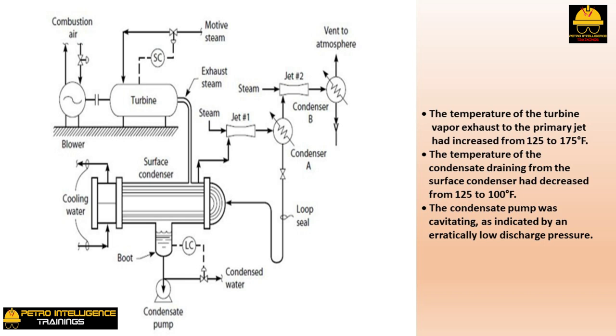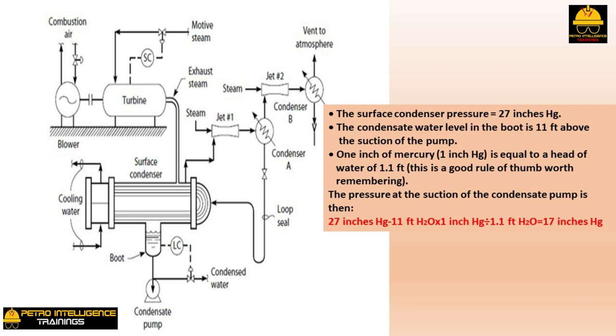Condensate pumps serving surface condensers have a common problem: their suction is under vacuum. For example, with the surface condenser pressure at 27 inches mercury and a condensate water level in the boot 11 feet above the pump suction — using the rule of thumb that 1 inch mercury equals 1.1 feet of water head — the pressure at the suction of the condensate pump is 27 inches mercury minus (11 feet ÷ 1.1) = 17 inches mercury. If the seal of a centrifugal pump leaks under vacuum, air will be drawn in and the pump's capacity will be severely reduced.